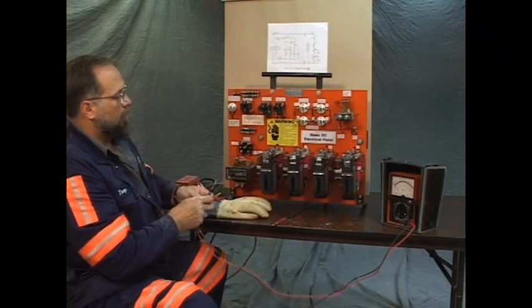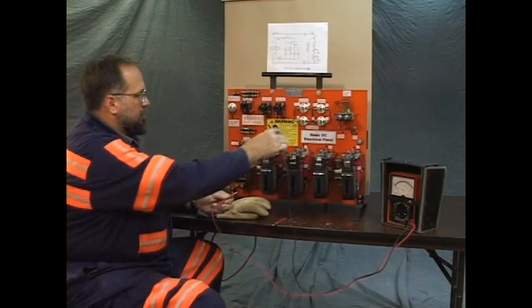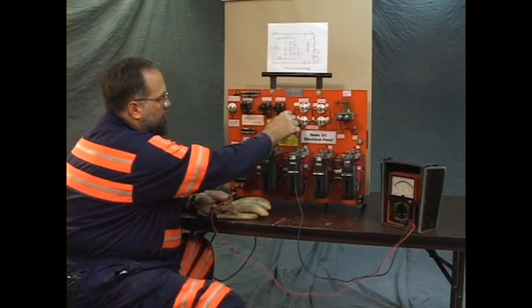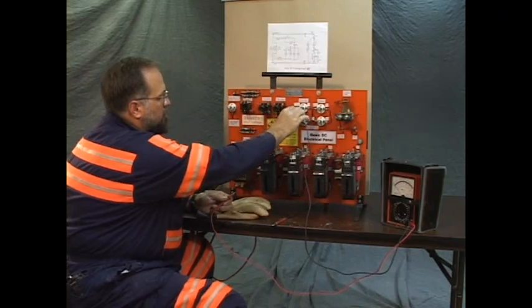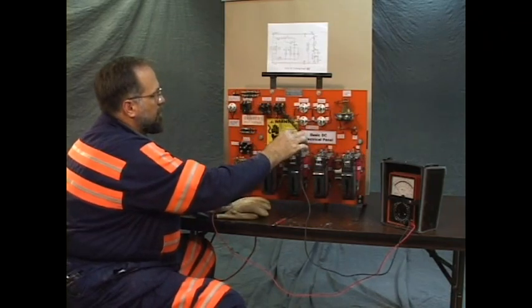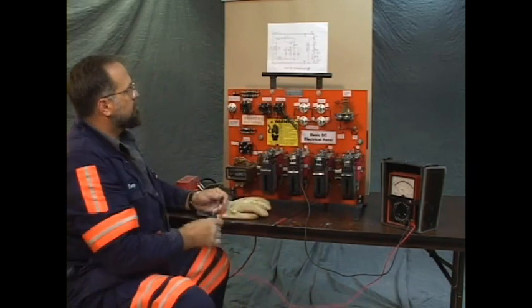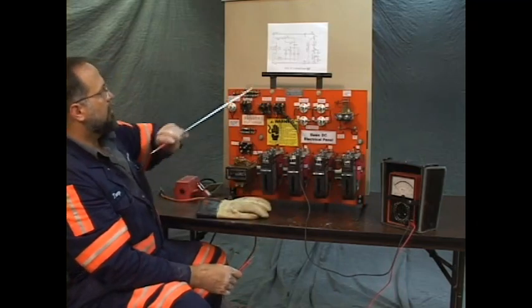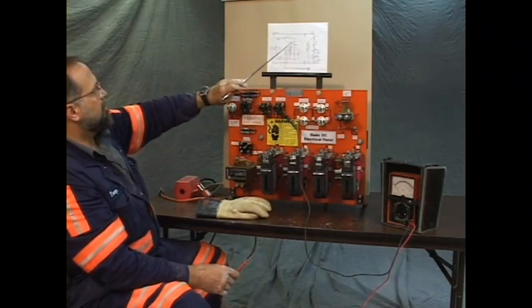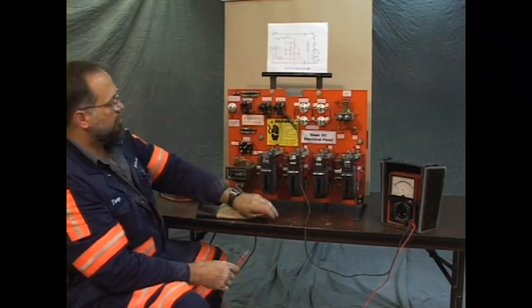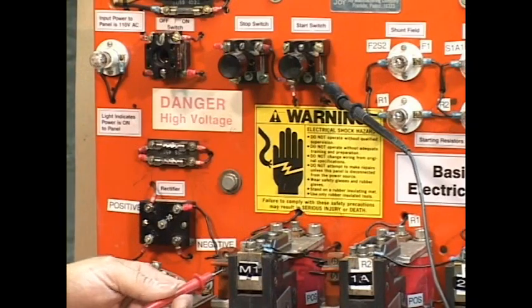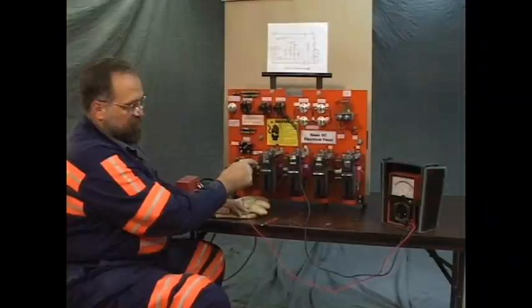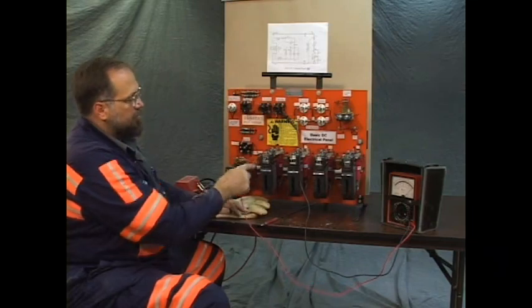Well, while we're here, let's just check the other side of that mercury switch. We're going to test the load side of the start switch. On the print, that would be here, to the load side of the mercury tube, which is the bottom of the mercury tube. That part of the circuit, as the meter indicates, is intact.